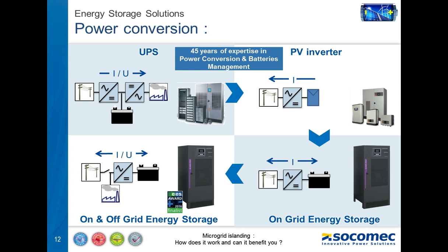Socomec has a long experience in the field with its UPSs, which include battery management and power conversion management that Socomec has been developing for 45 years. Linked to this experience, it was logical to start developing the PV inverters, which are unidirectional converters working as a current generator. Then in 2013, Socomec launched its on-grid energy storage systems, which are bidirectional power converters acting as current generators only and only working as grid tied.